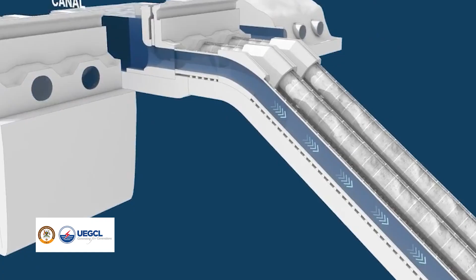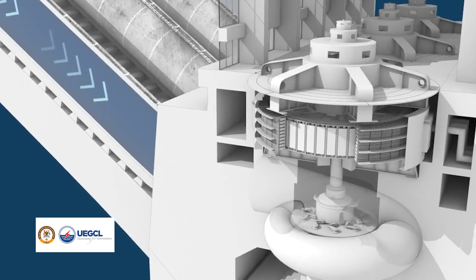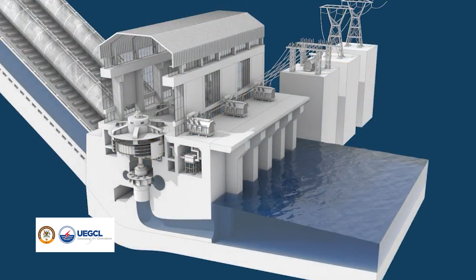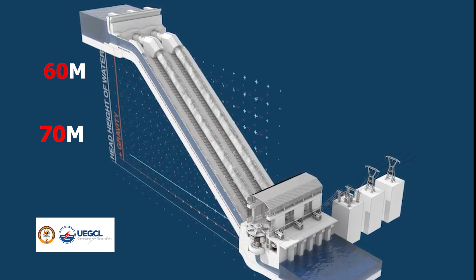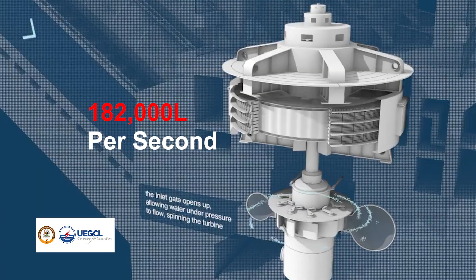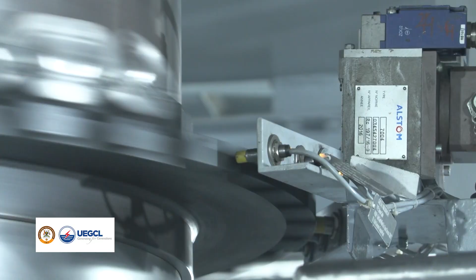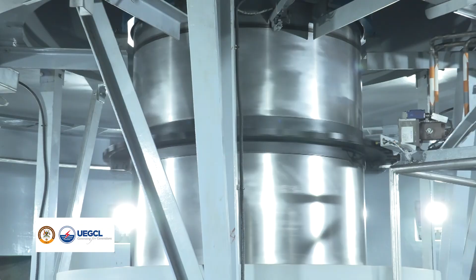When the inlet gate is open, water is released from the reservoir to the intake and falls through a penstock to the turbine. Each of the 6 installed turbine units is served by an independent intake inlet. From a head of 60 to 70 meters maximum, each turbine requires at least a volume of 182,000 liters per second to rotate and generate 100 megawatts.